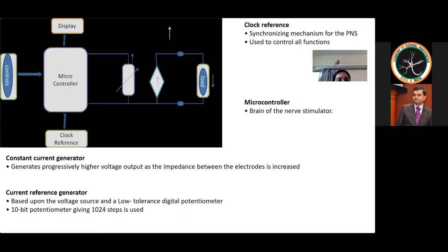Now coming on to the microcontroller, which is considered the brain of the nerve stimulator. This nerve stimulator basically runs on a battery, so low battery powered are preferred. Now this microcontroller will receive the input from the control, and this will help change the value of the current, frequency, and the pulse width. It relays the set value to the display so that the user gets aware of the new set. Then we have a constant current generator. An ideal current generator does not exist, as the current must be the same despite varying degrees of resistance. So this is achieved by generating progressively higher voltage output as the impedance between the electrodes is increased.